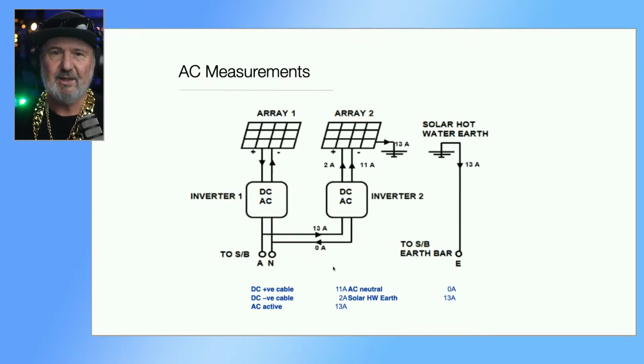And what they discovered, now this is using just a tong tester, an AC tong tester, so not DC current, AC current measuring here. They were seeing 13 amps on the active going into inverter number 2, and on the DC cables going to the roof, they saw 2 amps AC on the positive and 11 amps AC on the negative. There shouldn't be any AC up there, and it was flowing through an accidental bond to the roof, basically the screws that attach the mounting system to the roof, and then there was one of those solar hot water tanks on the roof with a heating element, and therefore it had a bonding earth, a protective earth, on the hot water service, and that was providing a return path back to the main switchboard to the earth bar. So there was 13 amps flowing through the earth conductor.